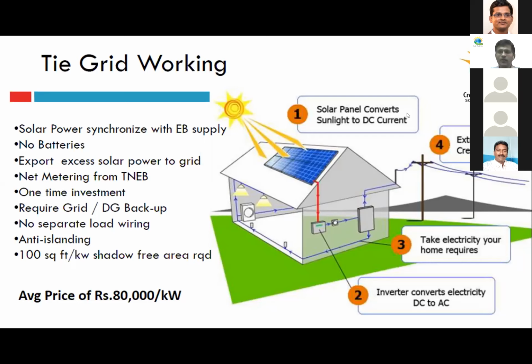And typically we require around 100 square feet per kilowatt. If you're using monocrystalline panels, it could come down to 60 to 70 square feet per kilowatt. The price is less than 80,000 per kilowatt, based on the size. The bigger the capacity of the plant, the lesser is the price. Let's say we're talking about a 100 kilowatt plant at a single premises with a single inverter. This could cost somewhere around 45,000 to 50,000 per kilowatt based on the installation, wiring lengths, and customization. And if you go with only 1 kilowatt, then it could touch around 80,000 per kilowatt.